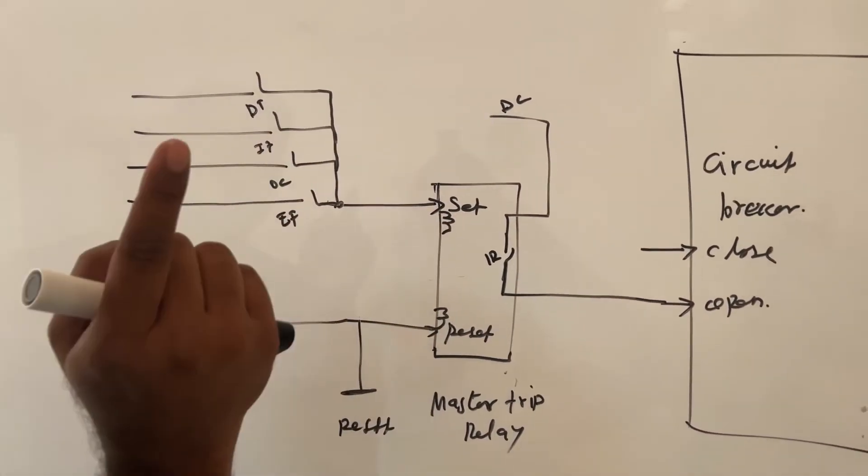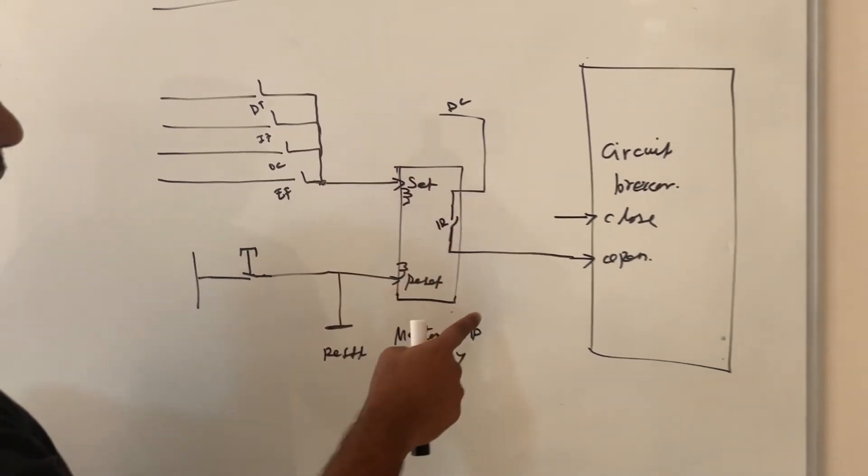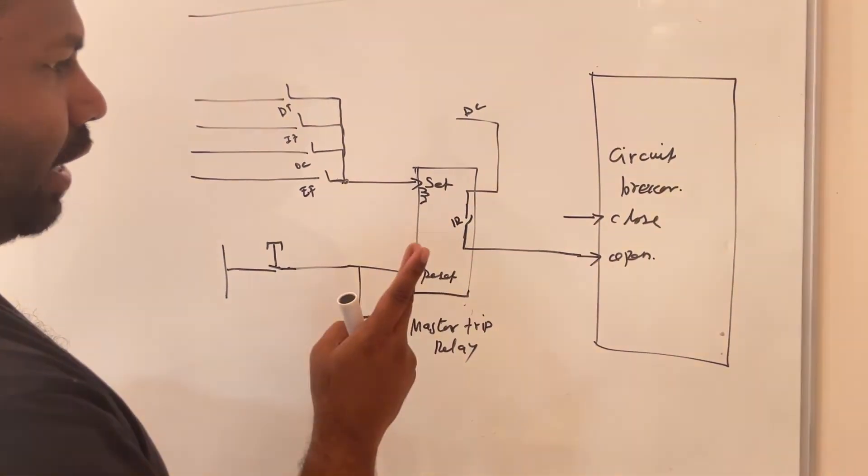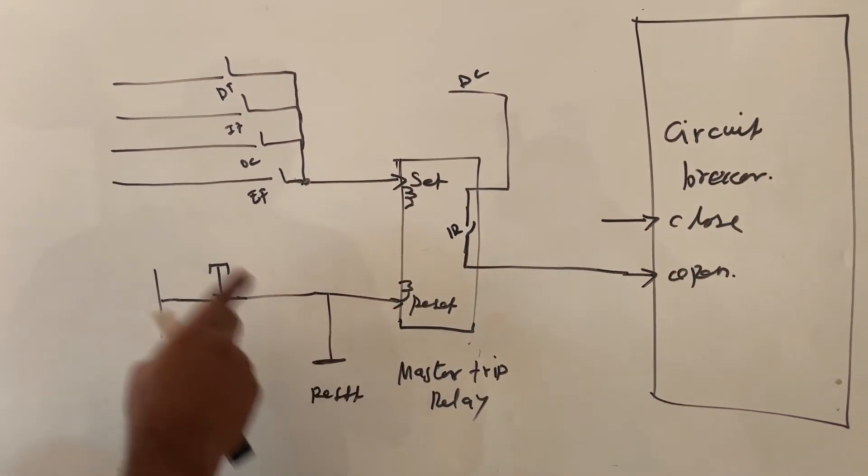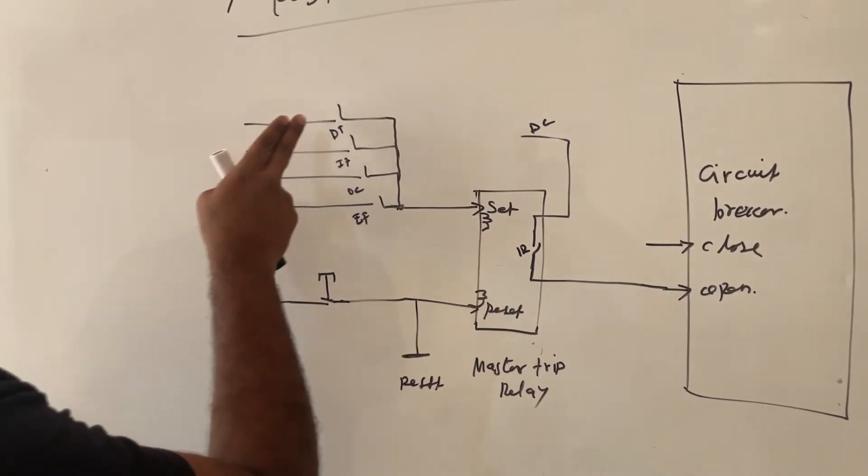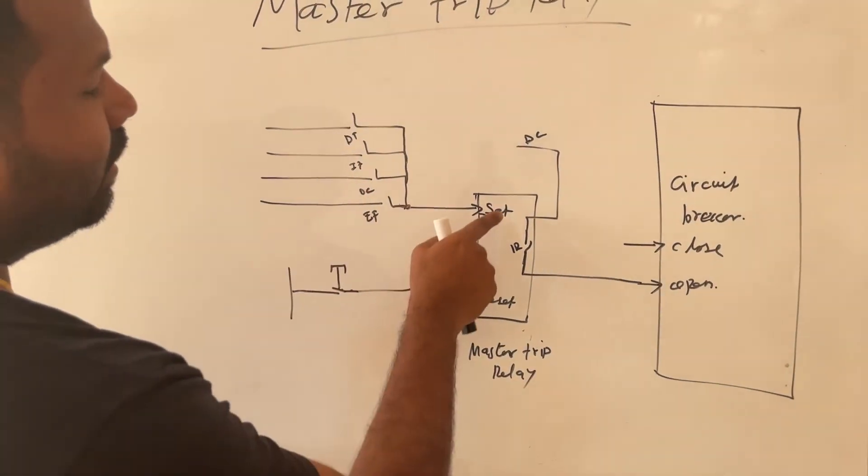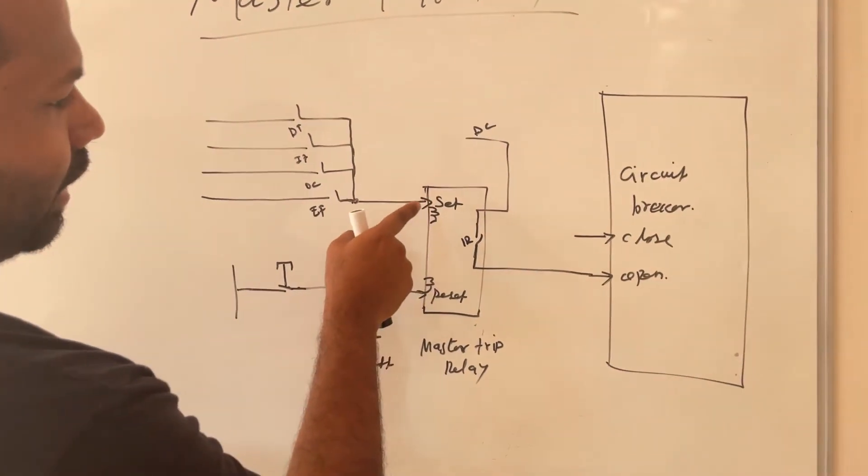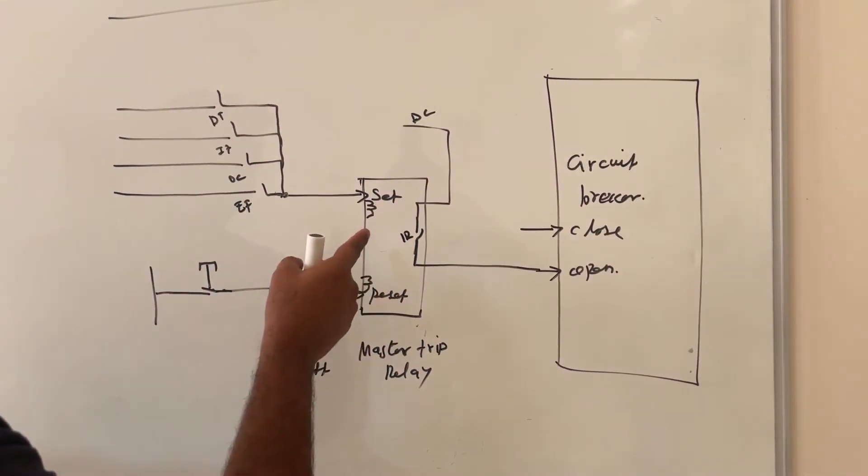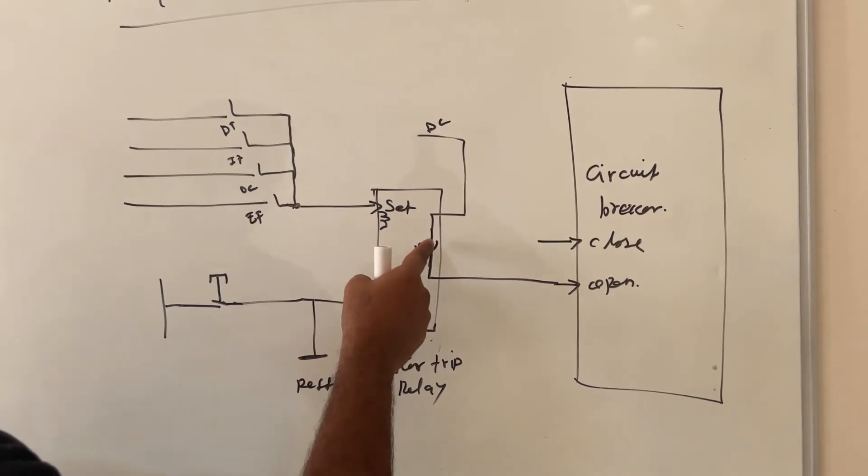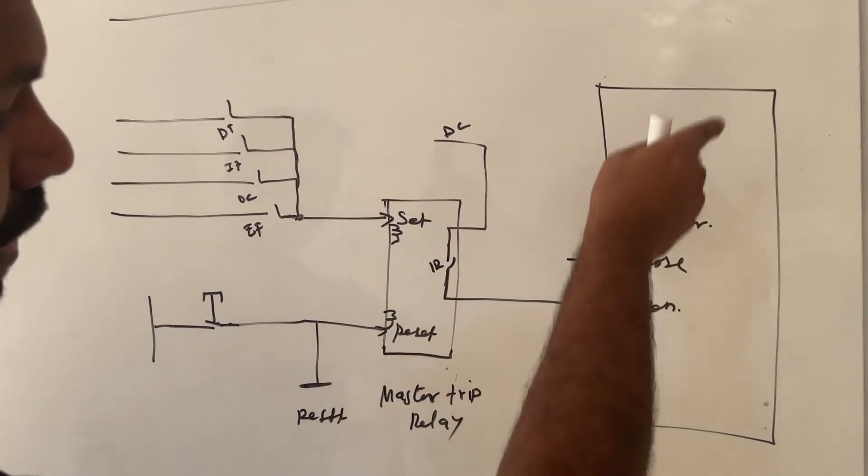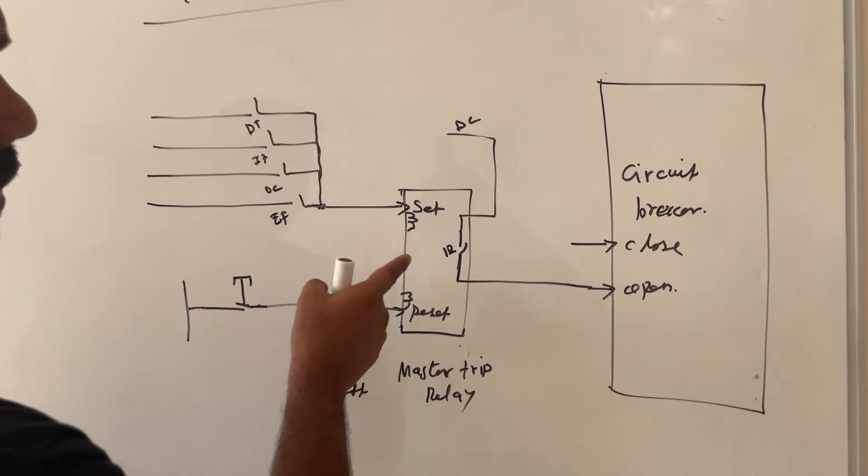This master trip relay will have two coils as I told you: one is set coil, another is reset coil. Once any external relay is activated, this will give signal to the set coil. Instantly this relay will activate, this relay will close the NO contact and it will open the breaker.